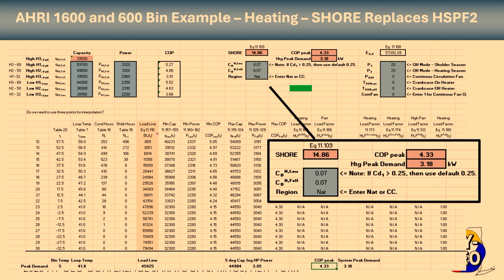This is typically done by the manufacturer and is not released, so you really don't know what these numbers are as a consumer. And so that's where some of the magic happens in here, is if you don't know what those numbers are to plug into this spreadsheet. But the result is a HSPF or a SEER. Now it's HSPF 2 and a SEER 2. And with the new standard, 1600, it's going to change to a new metric called SHORE for seasonal heating. And it's also got off cycle in there. That's what the O is for. And so SHORE is heating and SCORE is the cooling number.